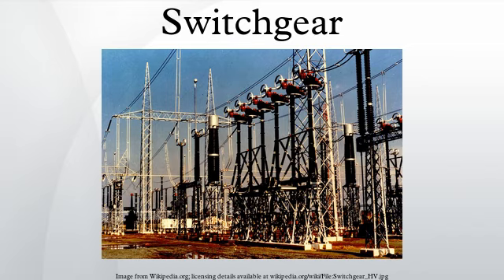By interrupting device: fuses, air circuit breaker, minimum oil circuit breaker, vacuum circuit breaker, gas circuit breaker, CO2 circuit breaker. By operating method: manually operated, motor stored energy operated, solenoid operated. By type of current: alternating current, direct current. By application: transmission system, distribution. By purpose: isolating switches, load break switches, grounding switches. A single lineup may incorporate several different types of devices, for example, air-insulated bus, vacuum circuit breakers, and manually operated switches may all exist in the same row of cubicles.